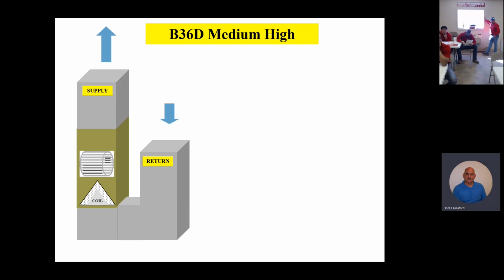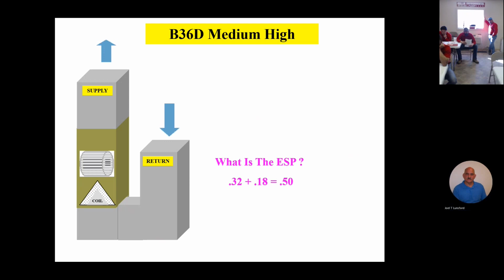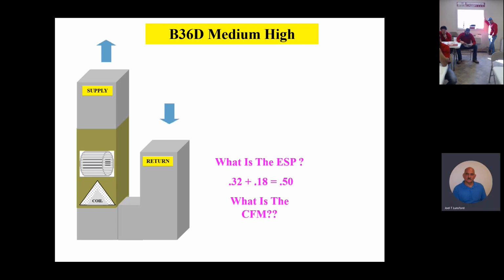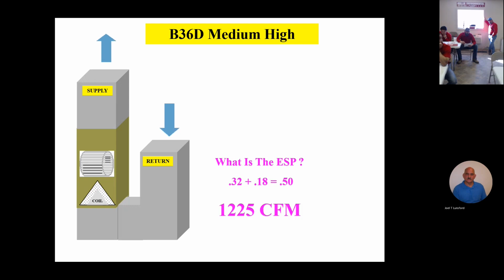Okay, good. Now, guys, this is important. You don't have to do algebra here. You don't have to do a negative number and a positive number. You just add the numbers up. So 0.32 plus 0.18 equals a 0.5 total. And it's a B36D on medium high speed tap. So what's the CFM off that chart? 1225. Okay, good. 1225. That's what I had too.